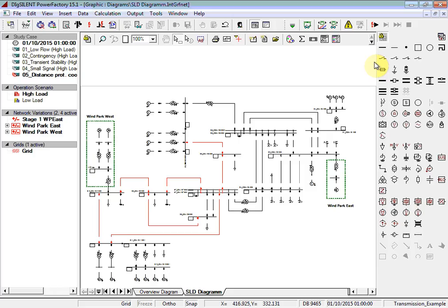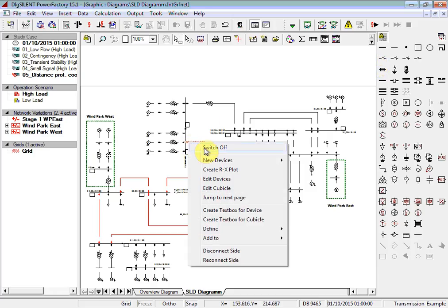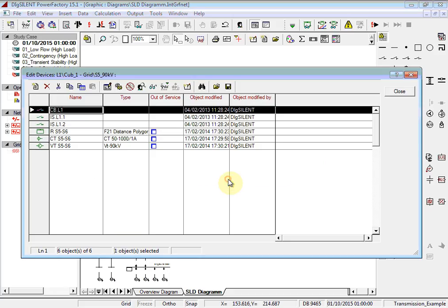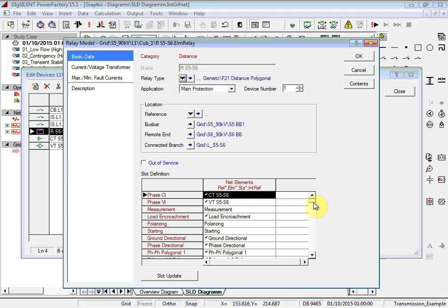We can take a closer look at the relay models installed in the network by right-clicking on a cubicle and choosing the option Edit Devices. Here, contained within the cubicle, you can see that there is a relay model, a current transformer model, a voltage transformer model, and 3 switching elements. Double-click on the relay model to take a closer look at its settings.